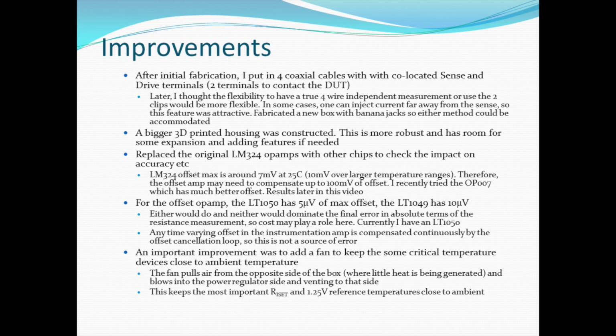And then we have the important improvement that I made, which is to add a fan to keep some of the critical temperatures inside the device fairly constant, close to ambient as much as possible. So the fan blows in air from the right side of the box where there's not much heating going on, and it pulls in cooler air and pulls it over the resistor and some of the reference areas, so it cools that a little bit. So the temperature rise is not as much as it used to be before. I think that definitely helped to improve the overall accuracy. But if there's a change in the ambient temperature, of course you're going to have some changes, and that's what I will show in my measurements.